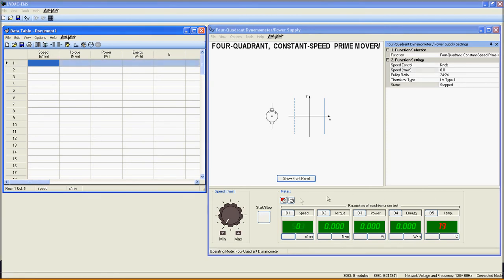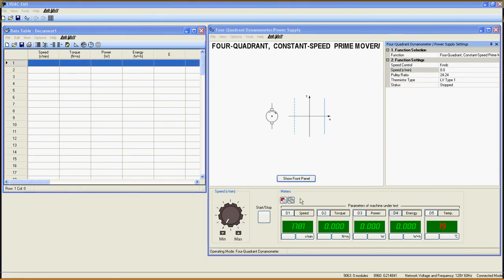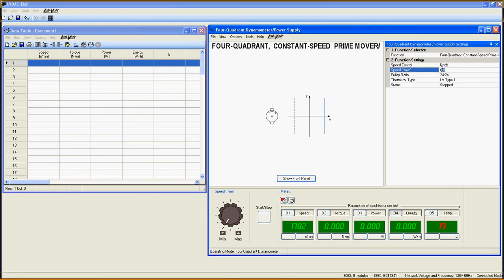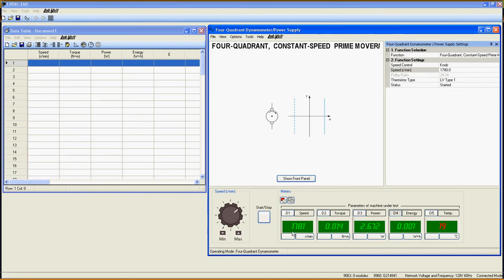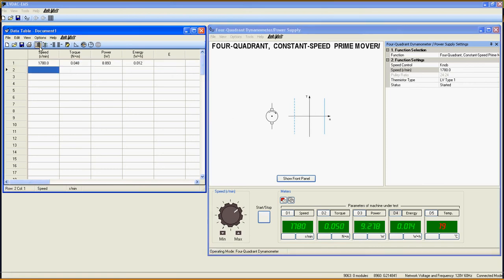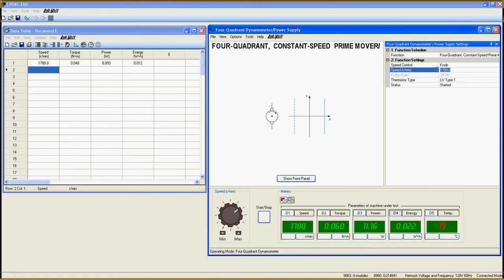First, I start my induction motor using a power supply connected to the power grid. Since my power grid is at 60 Hz, I can expect the induction motor to speed up to 1780 rpm. So I set the prime mover to a constant speed of 1780 rpm and start the function. Now this point is the neutral point between quadrant 1 and quadrant 4. I save these values using the data table.